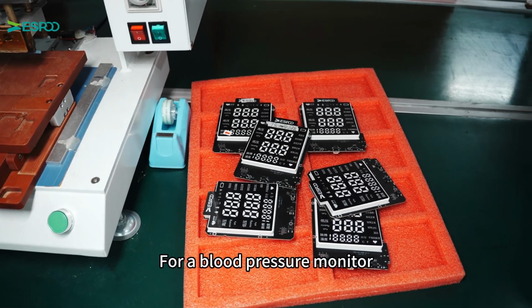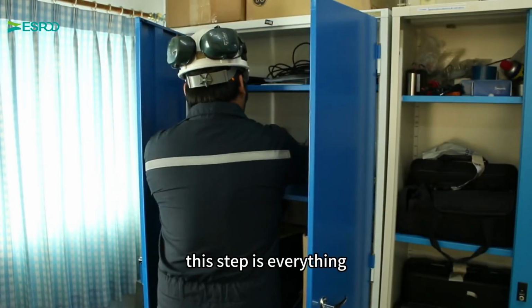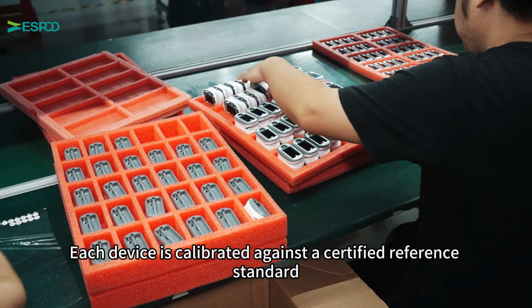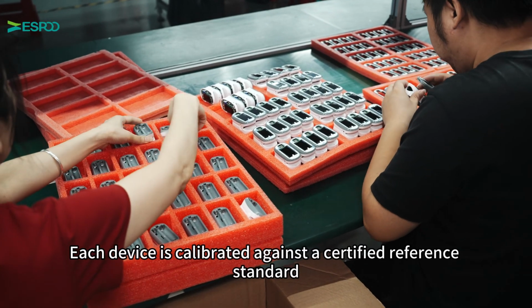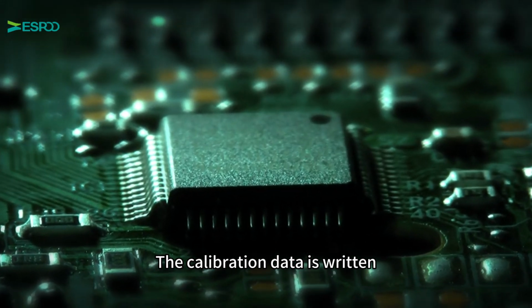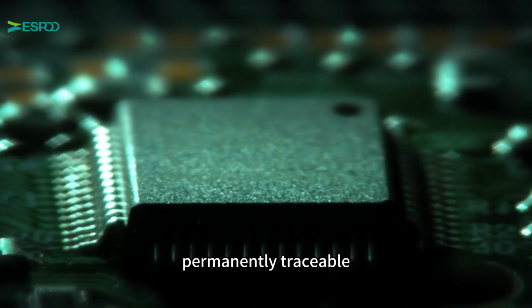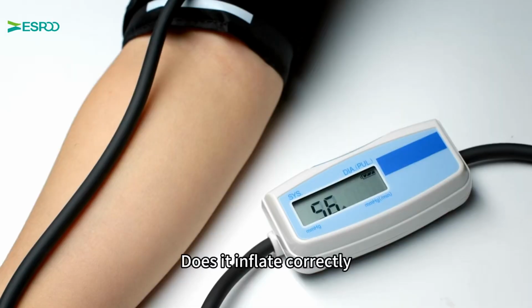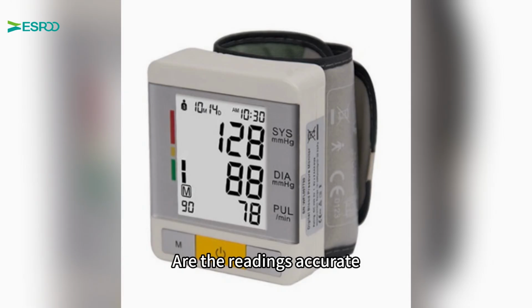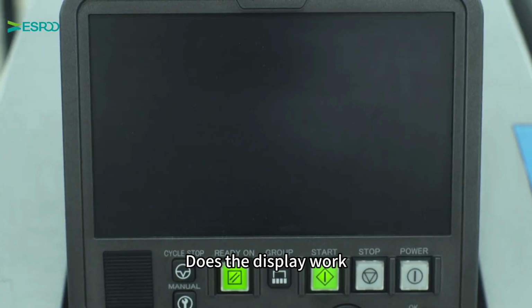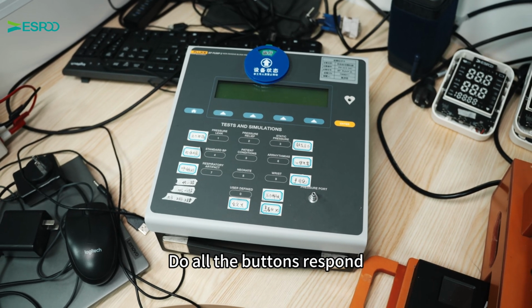For a blood pressure monitor, this step is everything. Each device is calibrated against a certified reference standard. The calibration data is written directly into the device's memory, permanently traceable. Station 5, functional testing. Does it inflate correctly? Are the readings accurate? Does the display work? Do all the buttons respond?